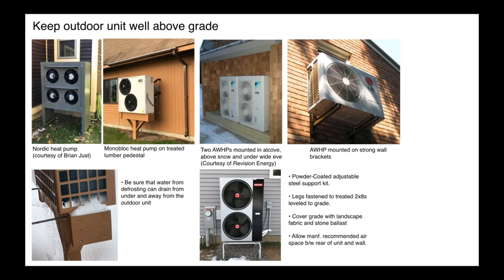Here is actually the unit in my office, and I tried to get a good snapshot to show you how fast that condensate comes off during a defrost cycle. When that outdoor coil frosts up, the unit will go into a defrost, and you're probably producing at least a quart and a half of water, and it's going to drop off of that coil. Now, if that's sitting on a slab at grade, it's going to freeze, and eventually you're going to create an ice bathtub around the bottom of that unit.